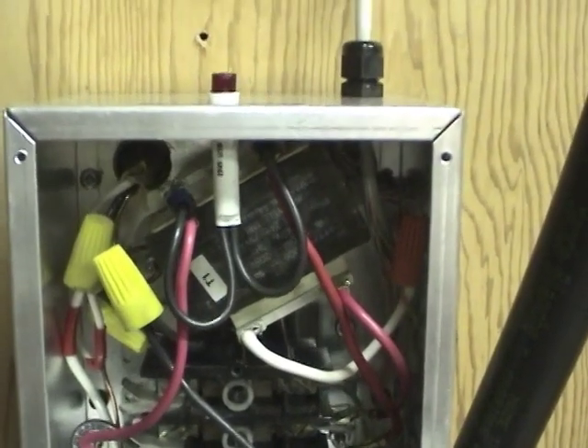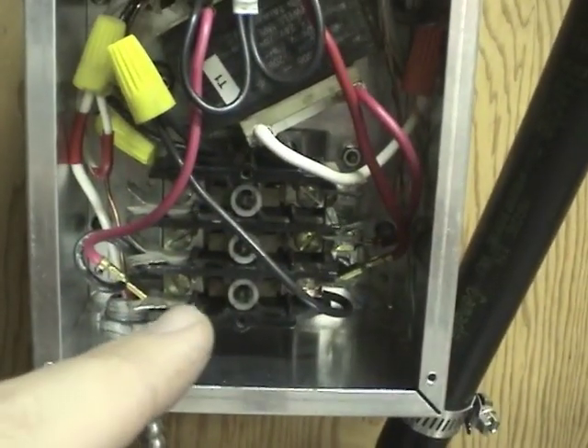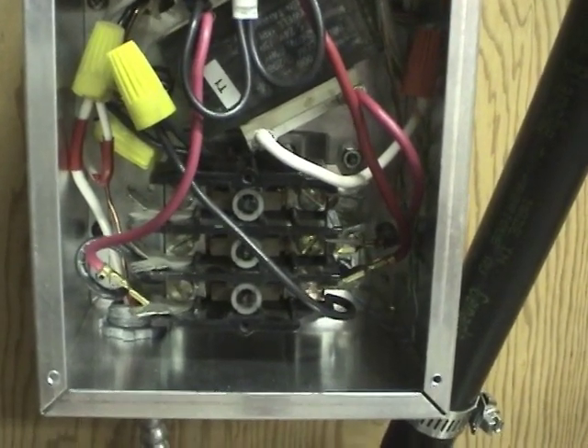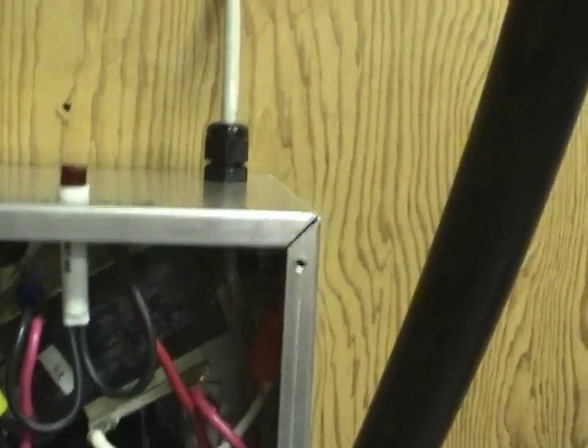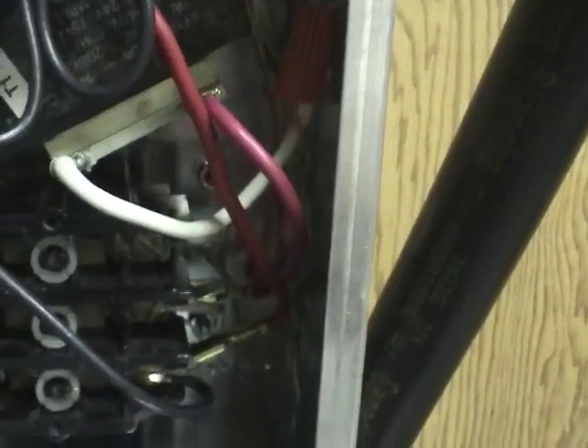In the control box you can easily see the 240V to 24V transformer. There's a contactor taken out of an old air conditioner — I think it was used to run the fan — it's originally three-phase but I'm just using one. I've also got a light to indicate when it's on. The signal from the water heater comes through this Cat5 cable; I just used one pair for each signal.